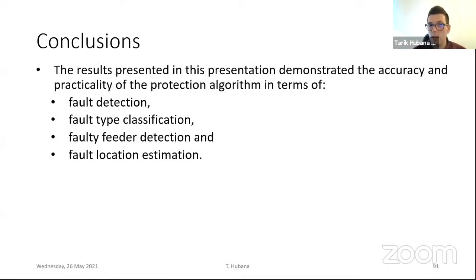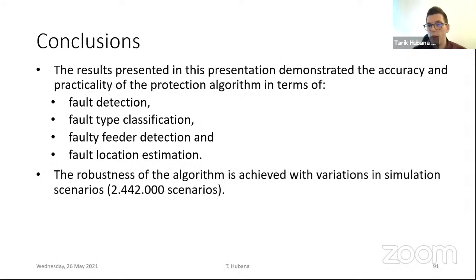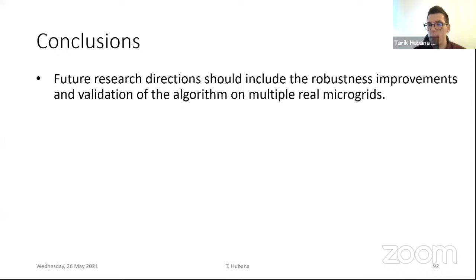In the end, the presented results of this research showed the practicability of these protection algorithms in terms of fault detection, fault type classification, faulty feeder detection, and fault location estimation. The robustness of the algorithm is achieved with all kinds of variations which may actually occur in a real system as well, in these different simulation scenarios, where we have almost 2.5 million simulation scenarios. Of course, this research doesn't stop.